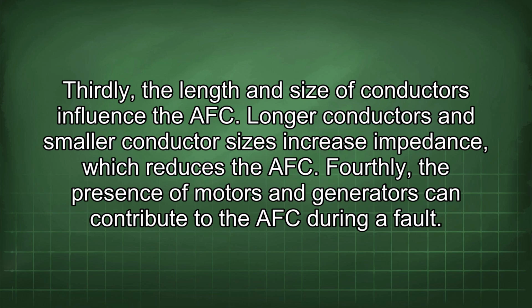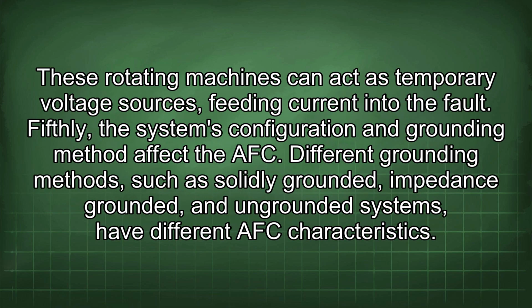Fourthly, the presence of motors and generators can contribute to the AFC during a fault. These rotating machines can act as temporary voltage sources, feeding current into the fault. Fifthly, the system's configuration and grounding method affect the AFC. Different grounding methods, such as solidly grounded, impedance grounded, and ungrounded systems, have different AFC characteristics.